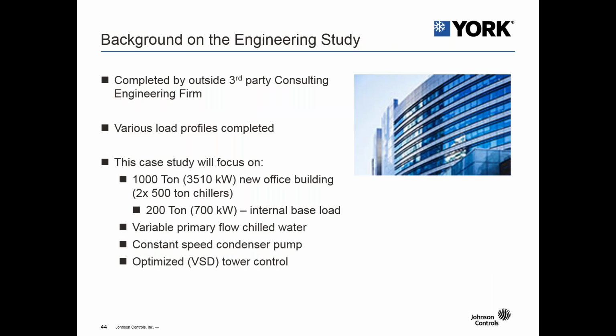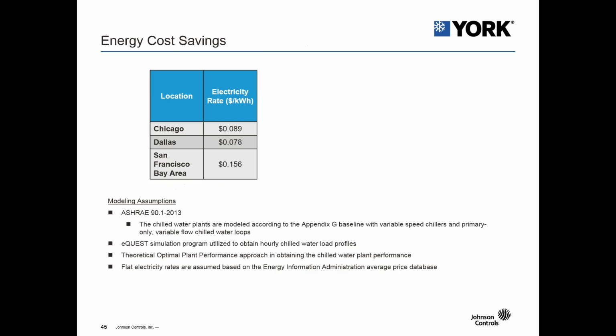So now we're going to go into an engineering study that we had completed by an outside third-party consulting firm. For this study, various load profiles were looked at, but we're going to focus for this presentation on a 1,000-ton new office building using two 500-ton chillers, and then the system has a 200-ton internal base load. We also looked at variable primary flow for the chilled water circuit and constant speed for the condenser loop, and optimized VSD tower control.